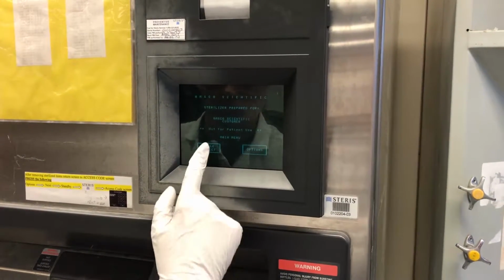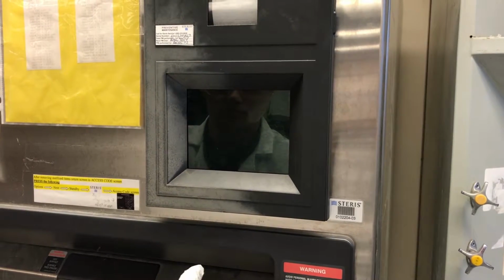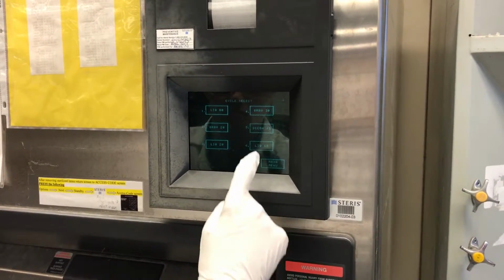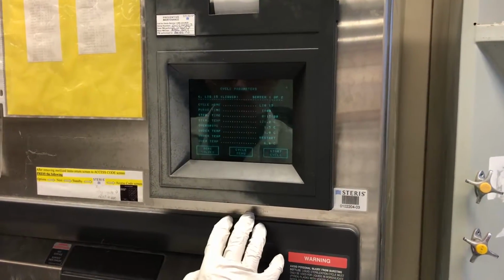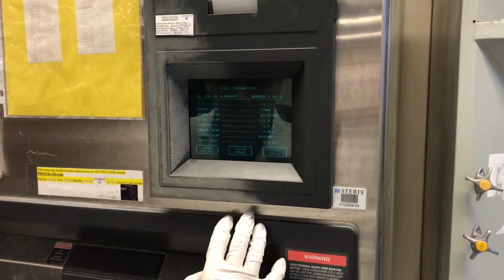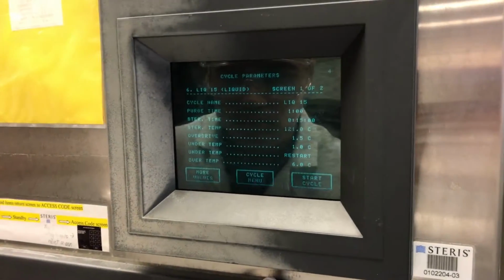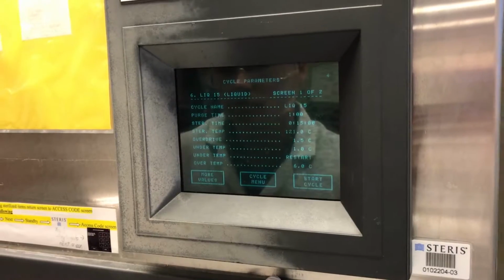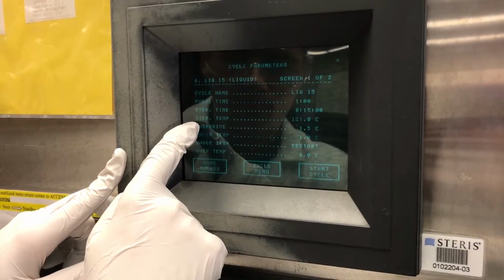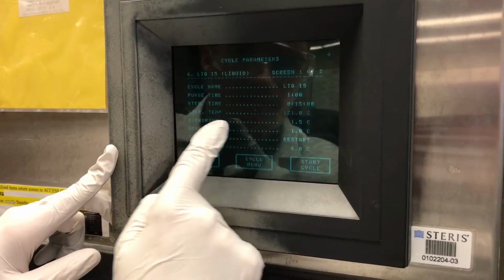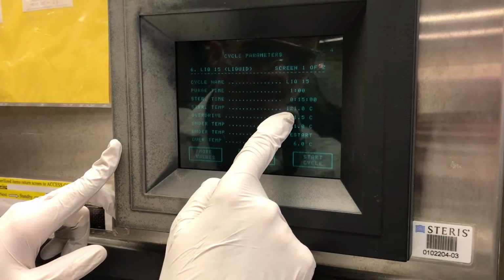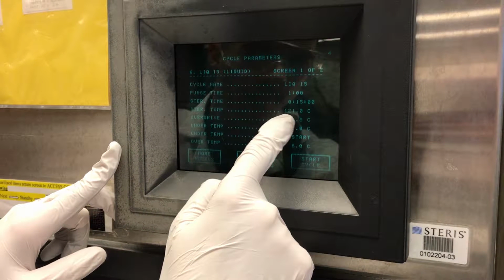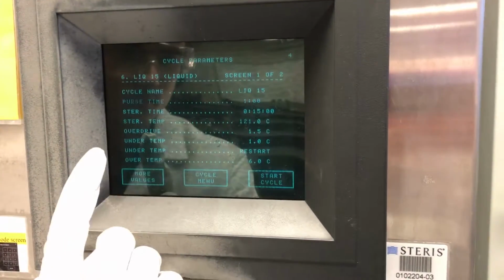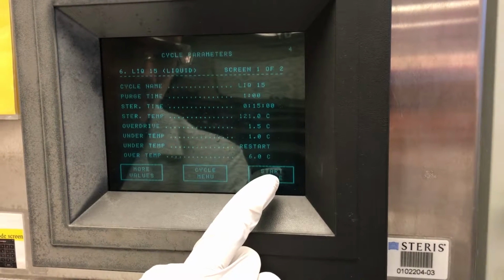After loading the machine, close the door and touch Cycle Select. Select the desired cycle and check that the sterilization temperature is 121 degrees Celsius. If the sterilization temperature is not 121 degrees Celsius, do not use the machine. In this case, follow the procedure in the Machine Alarm User Response section. Once the sterilization temperature of 121 degrees Celsius is confirmed, then touch Start Cycle.